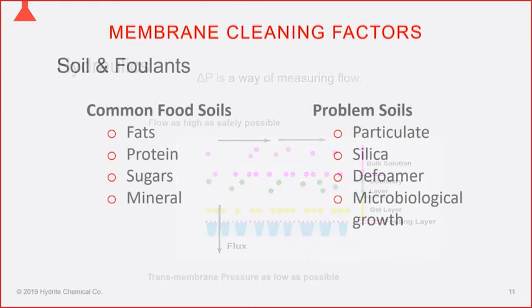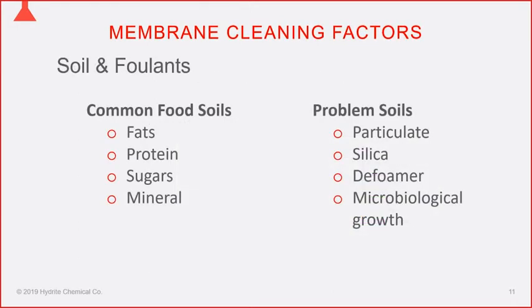For dairy processing, soils break down into four basic categories: fats, proteins, sugars, and minerals. The first three are organic soils and acidic in nature — you react those with caustics to help remove them. The final category, minerals, is alkaline in nature and requires an acid to remove. Those are the common food soils.